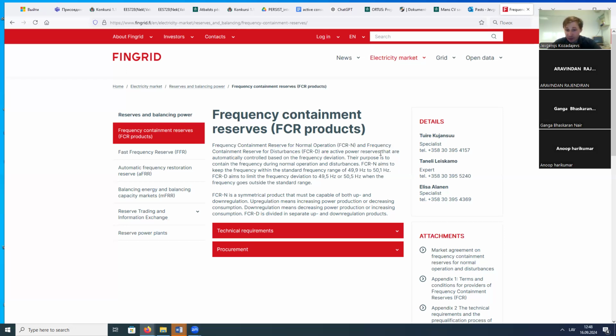These are active power reserves that are automatically controlled based on frequency deviation. Their purpose is to contain the frequency during normal operation and disturbances. FCR-N aims to keep the frequency within the standard frequency range of 49.9 to 50.1 Hz. So you see the range of deviation is very small - the normal is 50, so the deviation is 0.1, yeah, very small.